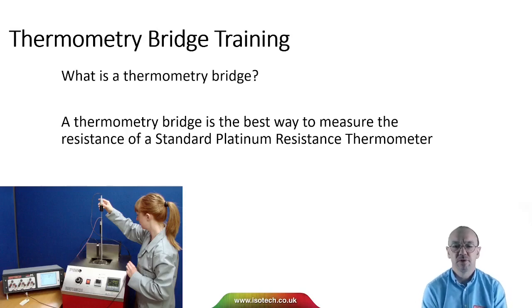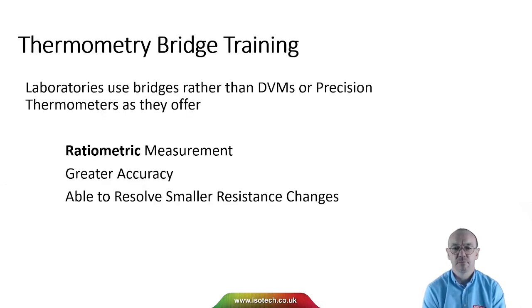Well, a thermometry bridge is the best way to measure the resistance of a standard platinum resistance thermometer in the calibration laboratory. And laboratories will use bridges rather than DVMs or precision thermometers because they offer ratiometric measurements, and with that greater accuracy and the ability to see very small resistance changes.